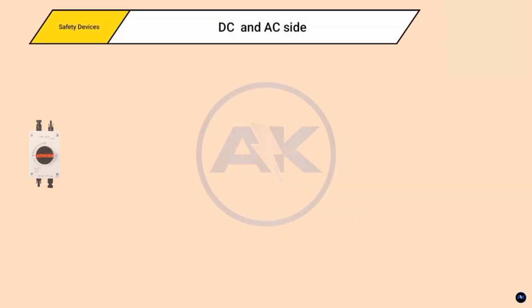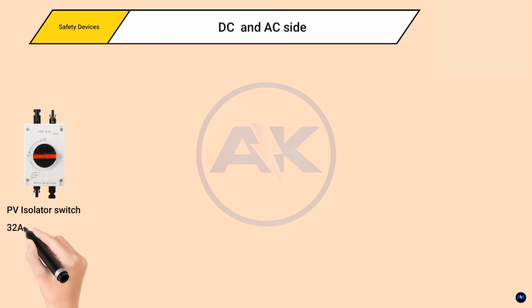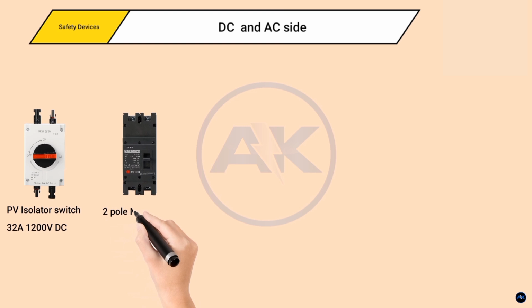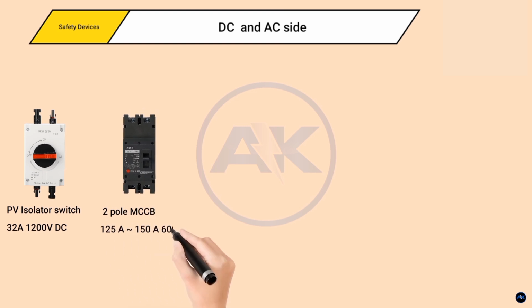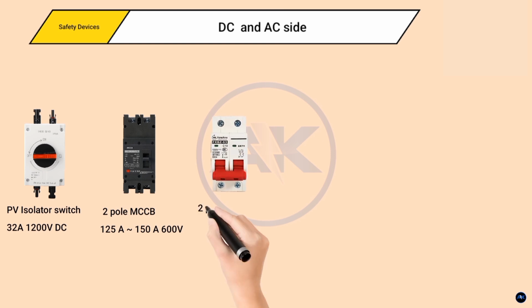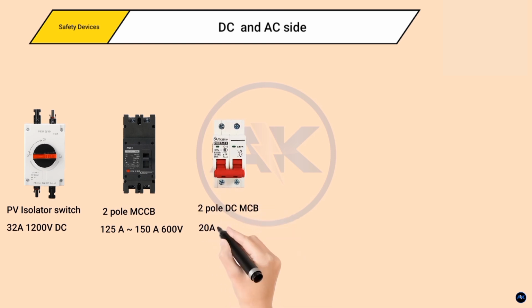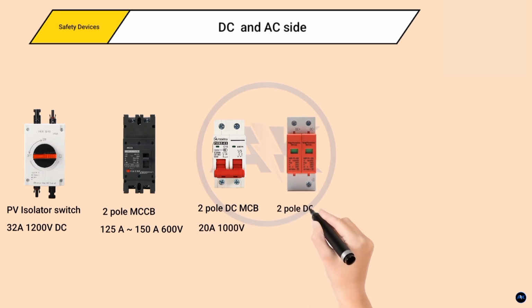First on the list we have our PV isolator switch rated 32 amps, 1200 VDC. We're going to use it as an isolator switch between the PV arrays and the DC MCB. Note that this will be optional. Second is the 2-pole MCCB. For 5 kilowatts of PMAX on your PV array, 150 amps, 600 volts DC is enough. The third is the DC MCB, or 2-pole DC MCB, rated 20 amps, 1000 volts. And next to that is the 2-pole DC SPD rated 20 to 40 kA, 500 volts.